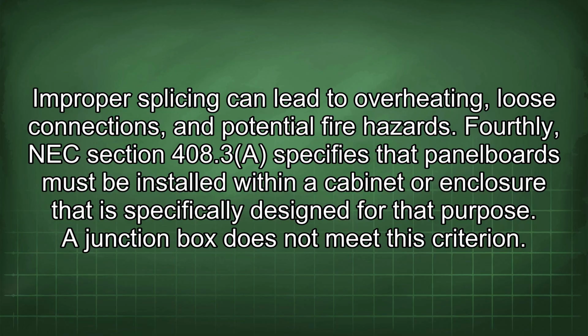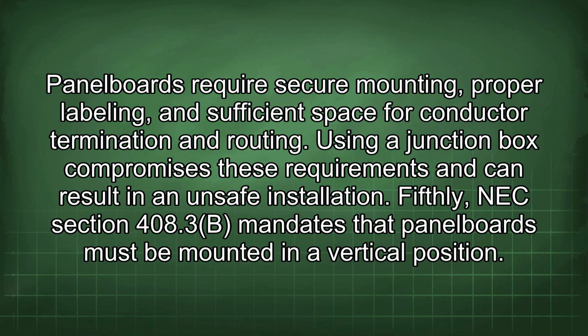Fourthly, NEC Section 408.3 specifies that panel boards must be installed within a cabinet or enclosure that is specifically designed for that purpose. A junction box does not meet this criterion. Panel boards require secure mounting, proper labeling, and sufficient space for conductor termination and routing. Using a junction box compromises these requirements and can result in an unsafe installation.